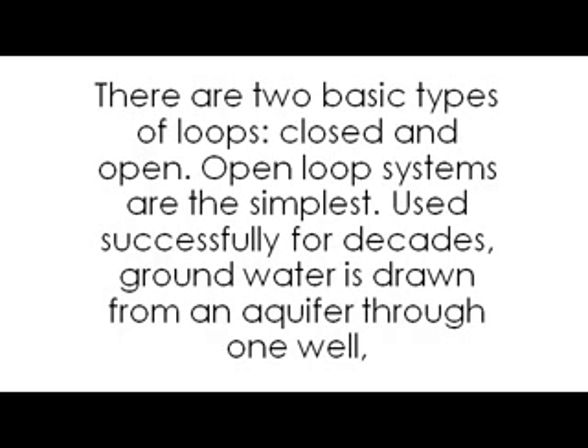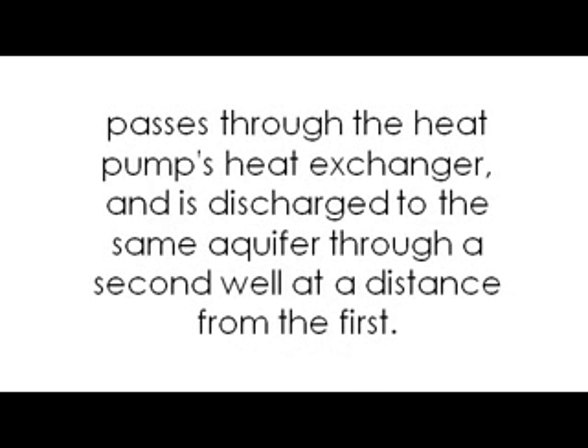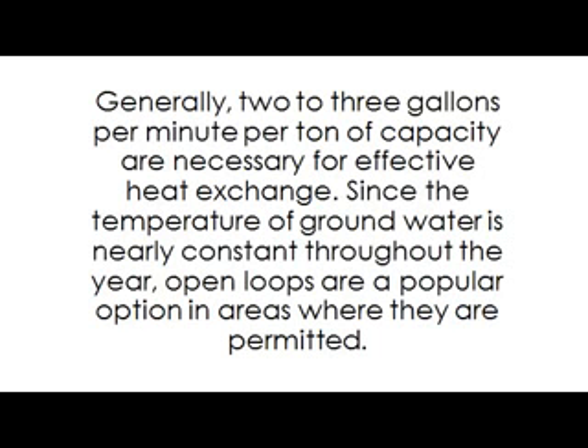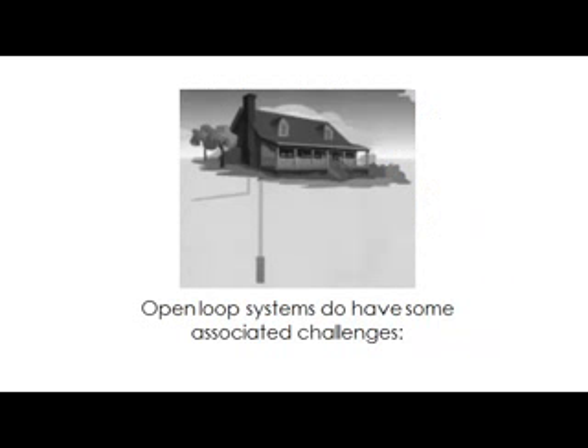Open loop systems are the simplest. Used successfully for decades, groundwater is drawn from an aquifer through one well, passes through the heat pump's heat exchanger, and is discharged to the same aquifer through a second well at a distance from the first. Generally, 2 or 3 gallons per minute per ton of capacity are necessary for effective heat exchange. Since the temperature of groundwater is nearly constant throughout the year, open loops are a popular option in areas where they are permitted. Open loop systems do have some associated challenges.